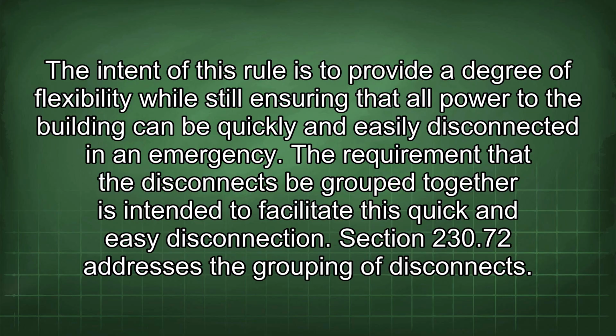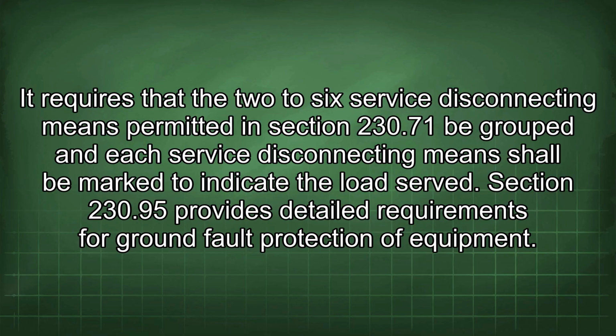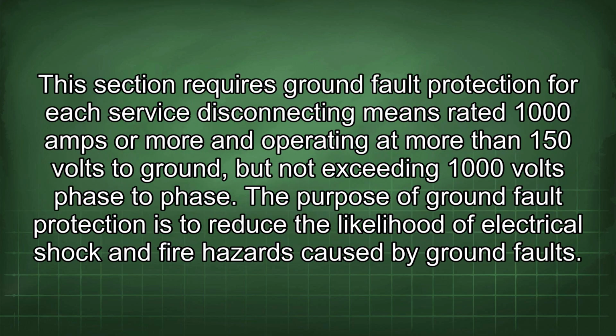Section 230.72 addresses the grouping of disconnects. It requires that the 2 to 6 service disconnecting means permitted in Section 230.71 be grouped, and each service disconnecting means shall be marked to indicate the load served. Section 230.95 provides detailed requirements for ground fault protection of equipment. This section requires ground fault protection for each service disconnecting means rated 1000 amps or more and operating at more than 150 volts to ground, but not exceeding 1000 volts phase to phase.